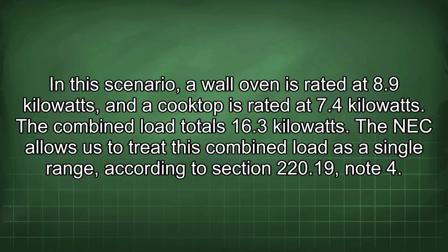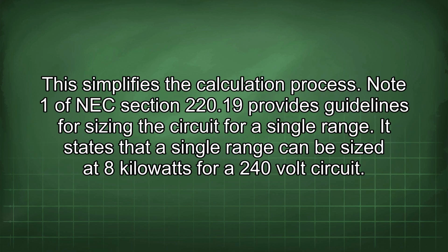In this scenario, a wall oven is rated at 8.9 kilowatts and a cooktop is rated at 7.4 kilowatts. The combined load totals 16.3 kilowatts. The NEC allows us to treat this combined load as a single range according to Section 220.19, Note 4. This simplifies the calculation process. Note 1 of NEC Section 220.19 provides guidelines for sizing the circuit for a single range. It states that a single range can be sized at 8 kilowatts for a 240-volt circuit.